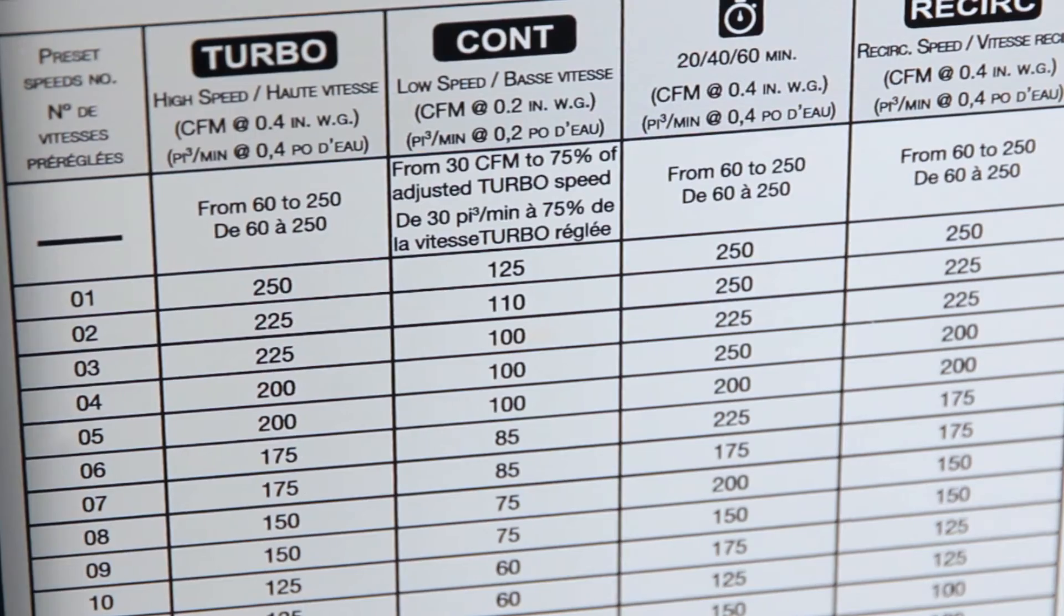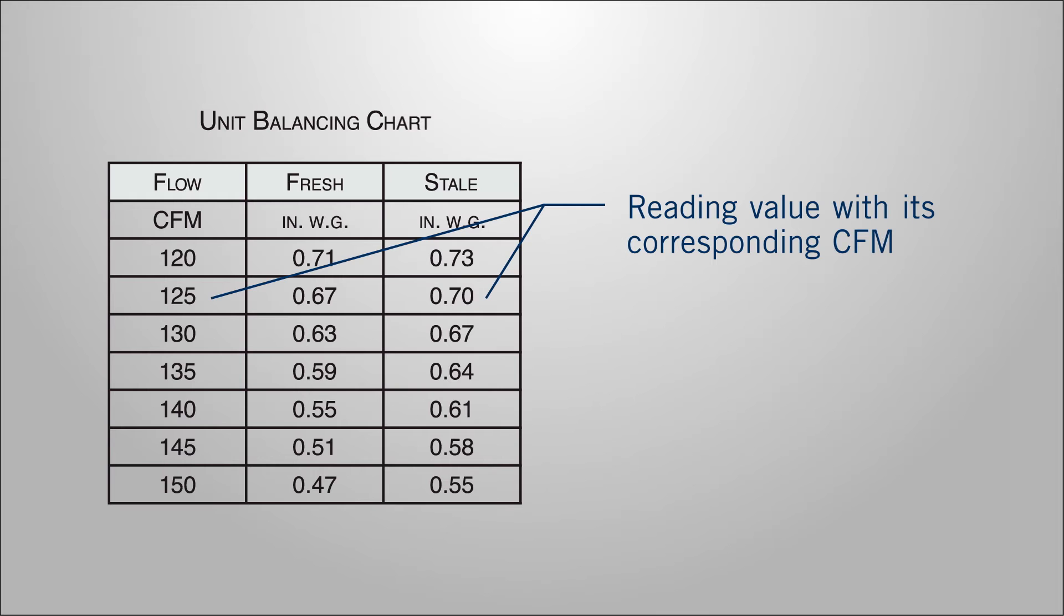The unit balancing chart and the unit preset speed table are affixed on the unit behind the right panel. Use the balancing chart to convert pressure values read from the pressure gauge to airflow CFM values. While balancing, the wall control screen displays which airflow to connect the pressure gauge.